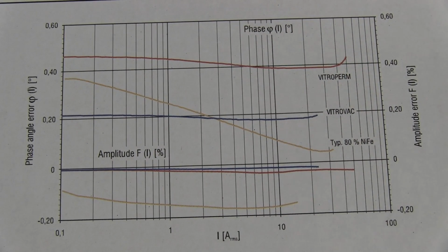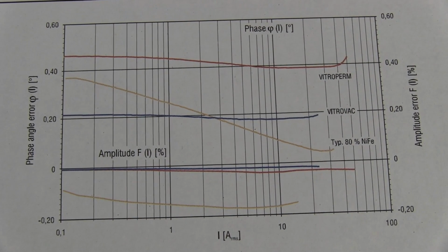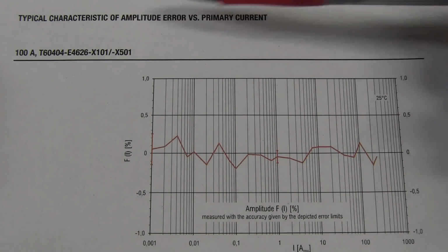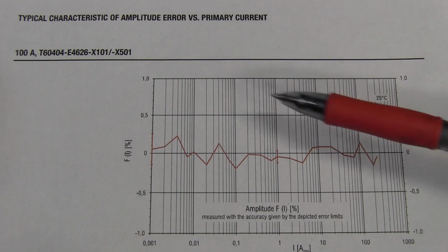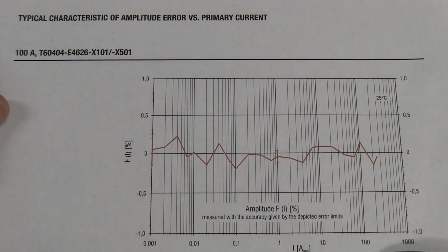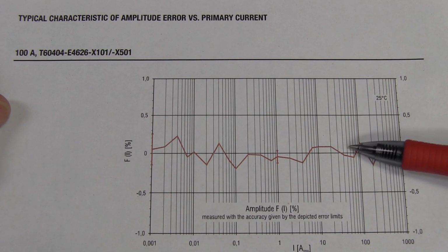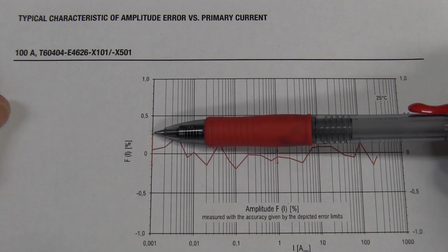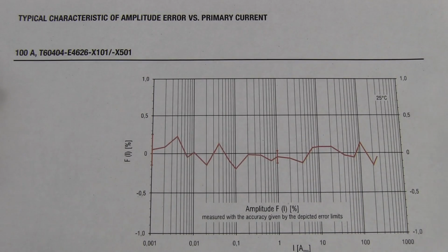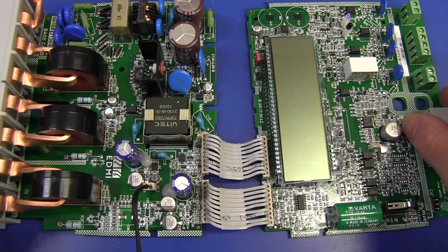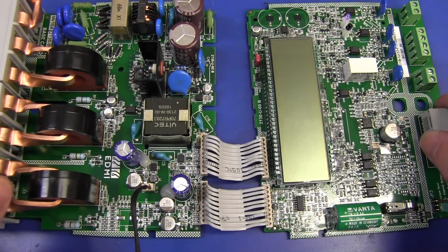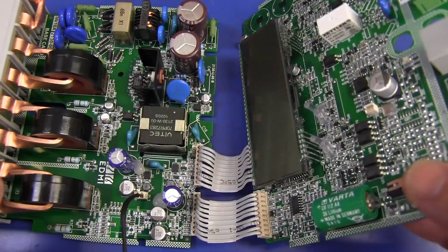So really, they've got some whiz-bang core technology that makes these pretty linear current transformers. I like them, and they've gone to town here. They've even got typical characteristics of the amplitude error versus the primary current over the full current range, from 1 milliamp all the way up to past 100 amps, and you'll note that it's only barely even plus minus 0.25% amplitude error.